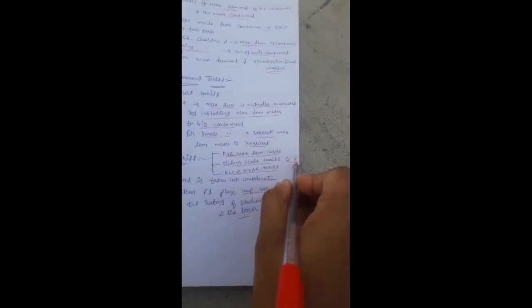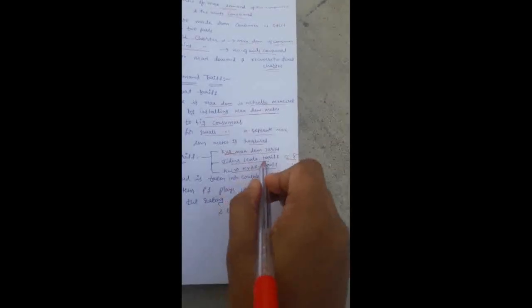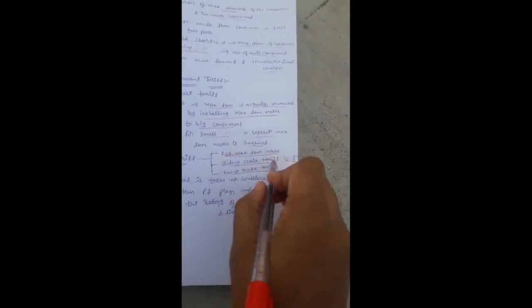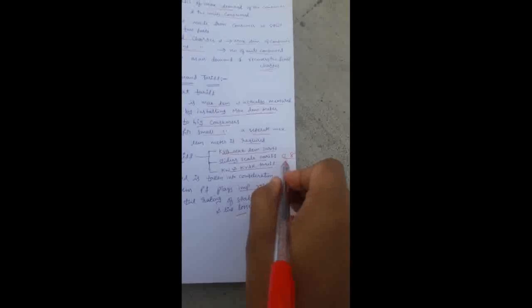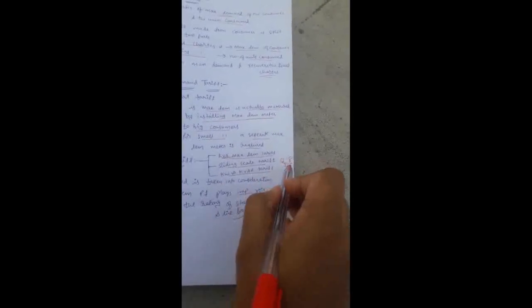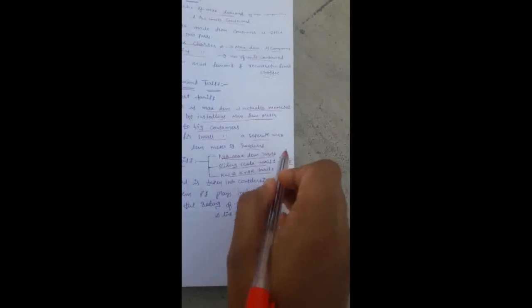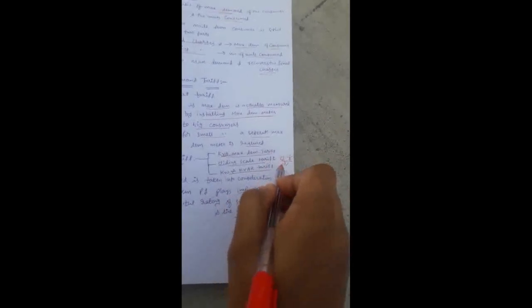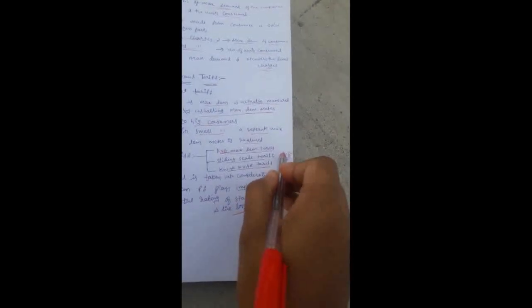They take 0.8 lagging as the reference. If the power factor of the consumer falls below 0.8, there will be additional charges. If it is above 0.8, they will give a discount.